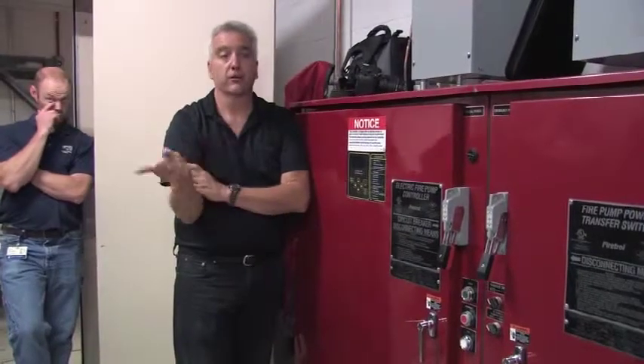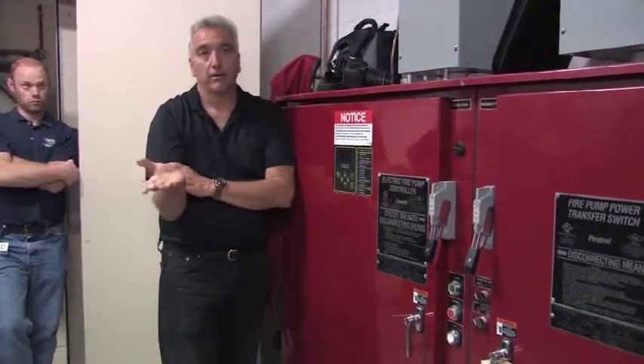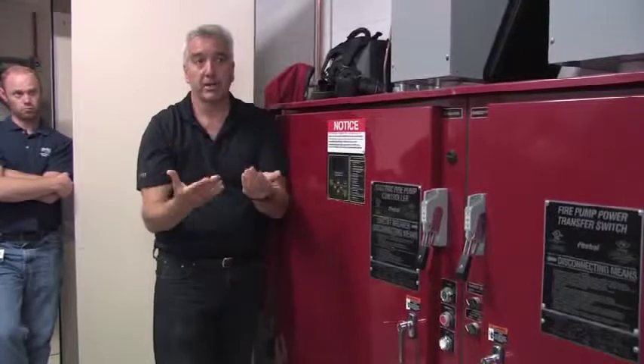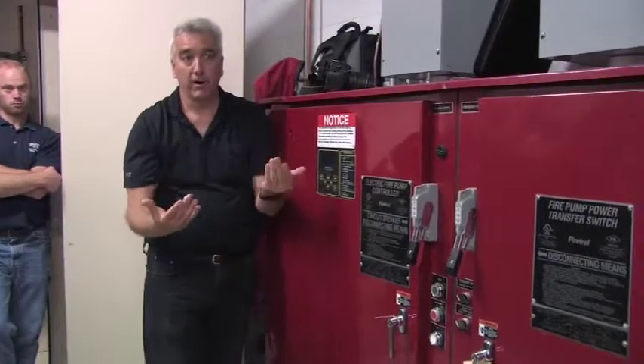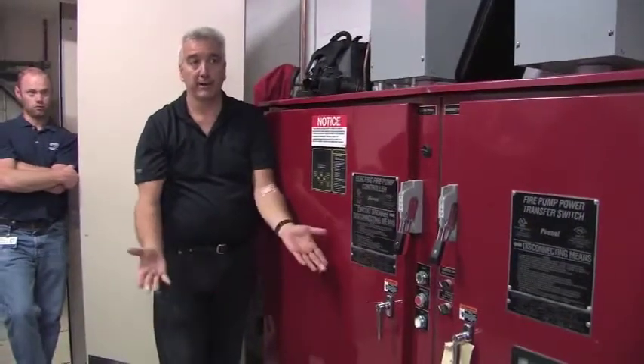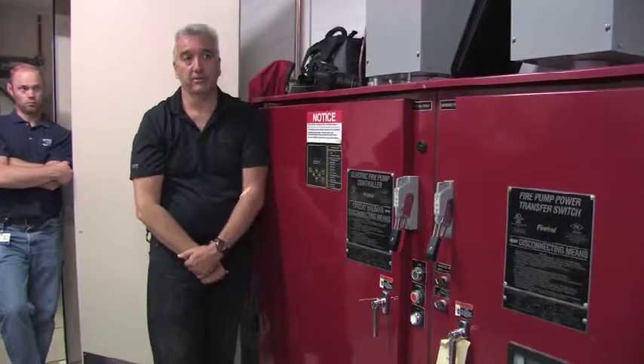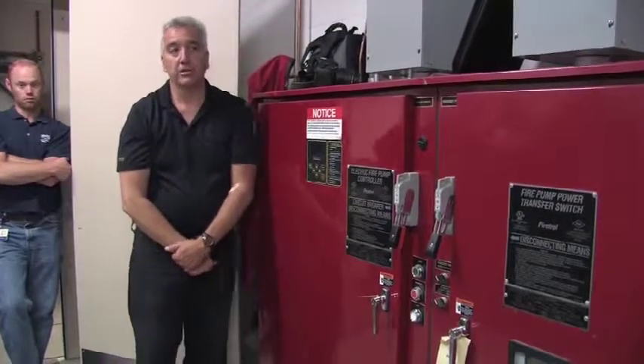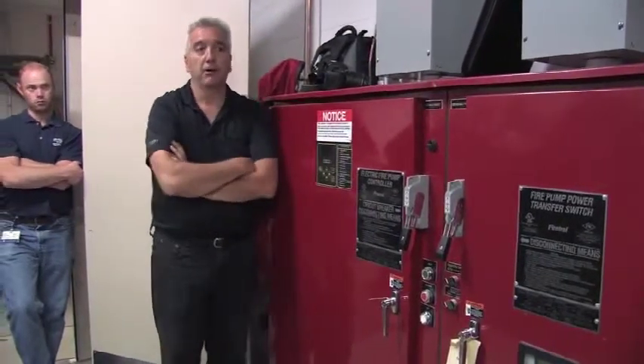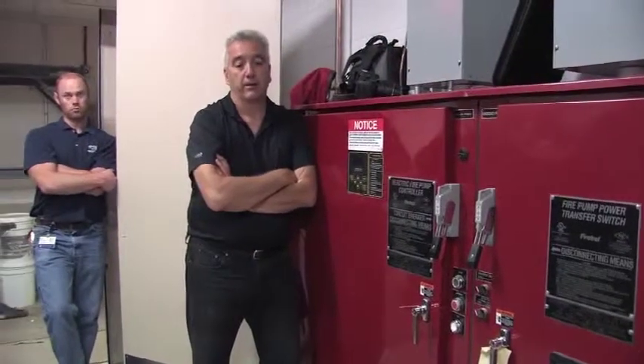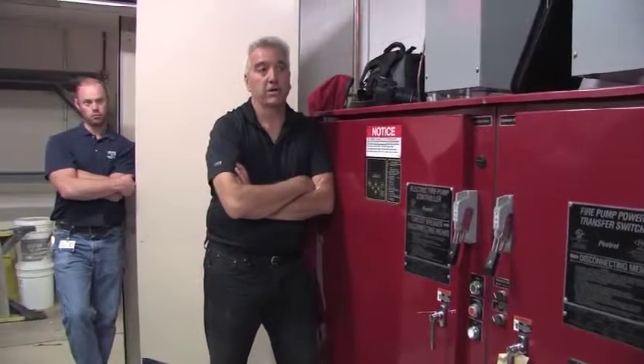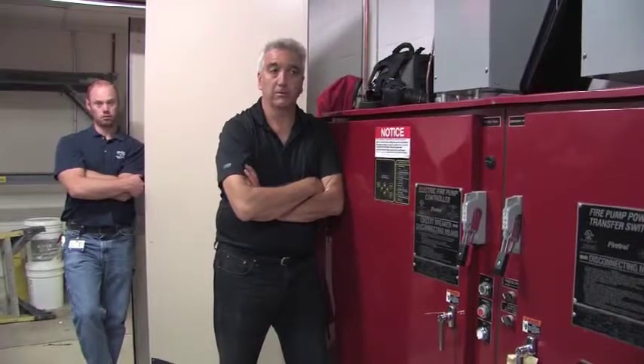We had a question as to whether or not you should rat race. Typically, a churn test is just that, a churn test, where you don't bother rat racing, you just start your pump up and let it run deadhead. It's called a deadhead test or a churn test. The only issue you've got is overheating the pump, because some pumps, depending upon the size, if you let them run for 10 minutes, might get very, very hot. Some of them won't, they'll be cool as a cucumber. But some get real hot.